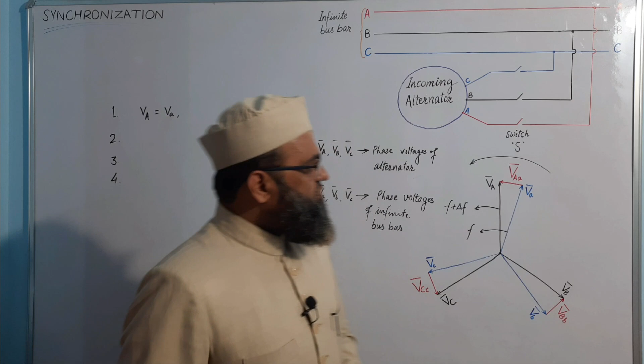One way is, just take a small three-phase induction motor and connect this induction motor one by one, once with this alternator, and see its direction of rotation, whether clockwise or anti-clockwise. Similarly, once this induction motor is connected with this infinite bus bar, again note down the direction of rotation, whether clockwise or anti-clockwise. If the direction of rotation in the two cases is same, it means that the two are having same phase sequences of the EMFs in three phases. Otherwise, we need to change the two terminals. Better to change the terminals of alternator. Otherwise, you may change the terminals of infinite bus bar also, any of the two. So this way, we can make the two phase sequences equal.